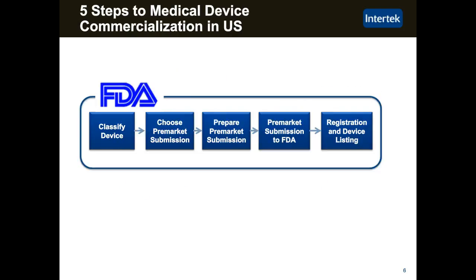So an overview of the 5 steps from an FDA point of view is you're going to classify your device. You're going to choose the pre-market submission pathway. You're going to prepare that pre-market submission packet that's going to go to the FDA. You're going to submit it. And then once you get approval from the FDA, you're going to register both your facility and your device, and then you'll be ready to go to market. So as I said, it's a fairly simplified version of what takes place, but we're going to cover the process in detail over the next 30 minutes or so.